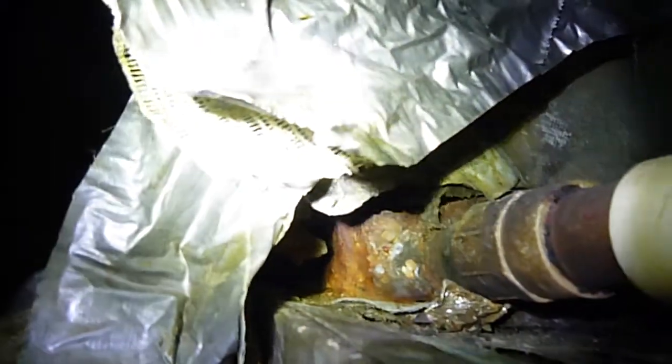Where does the drain line go? It keeps going — quite a run. Probably wasn't like that originally because it comes out of the closet. Something's been modified here, something's just not right. Then up in here, that's what your evaporator coil looks like — it's all rusty. It's time to replace the unit outside. There's your flue going up in there. All that tape — you don't think that leaks? No secondary drain line, no safety switch. A little more roof repair. That's your office.